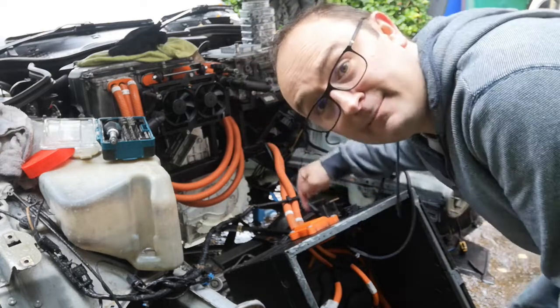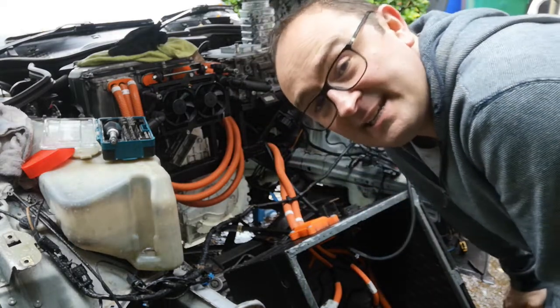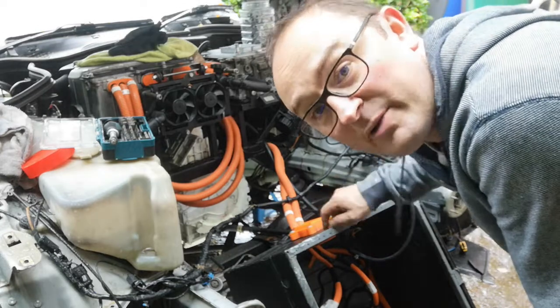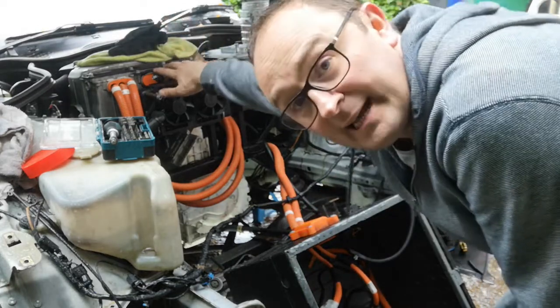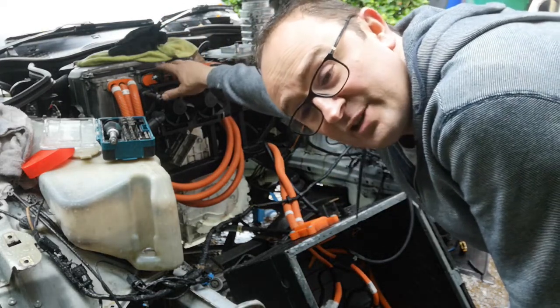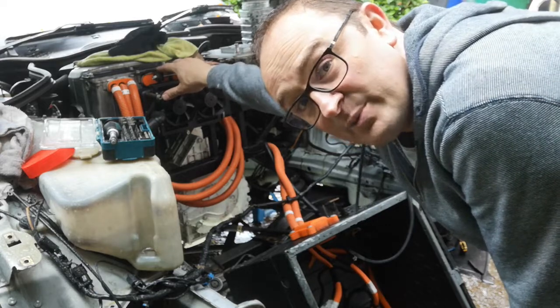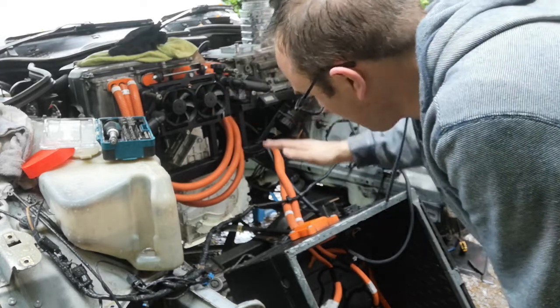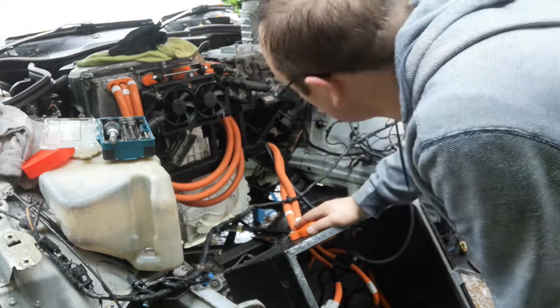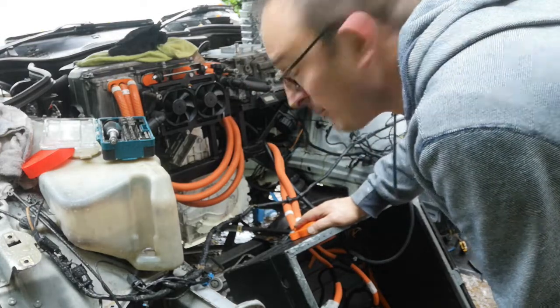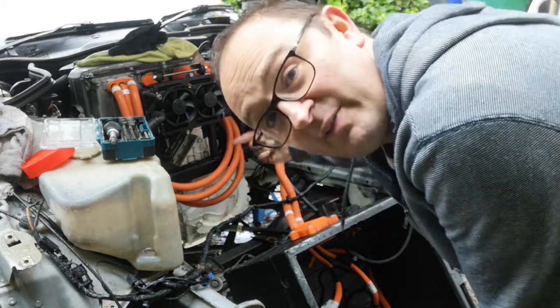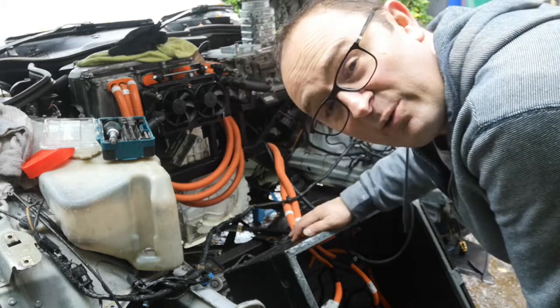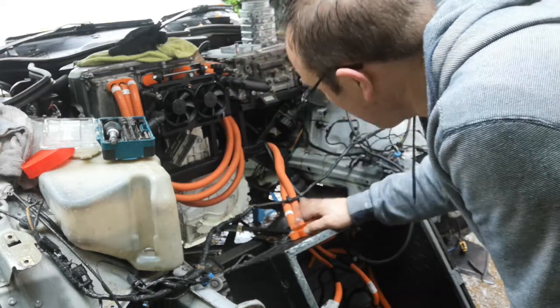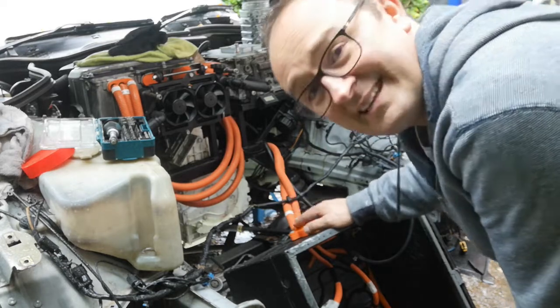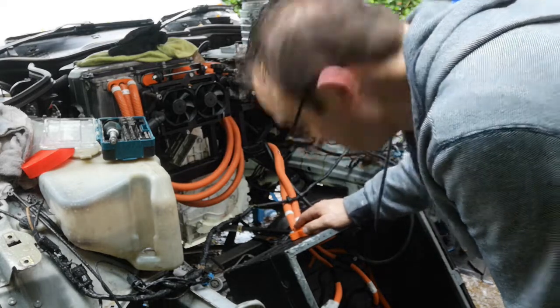What you can see here is the DC line, the high voltage running from the battery box up to the inverter. The inverter's been off and disconnected for ages, so those capacitors should be completely discharged. I can unbolt these, disconnect that, and work from there, because getting my hands in behind the inverter right now is a recipe for cuts and grazes, and stripping this thing down and rebuilding it in 8 hours is already hard enough.